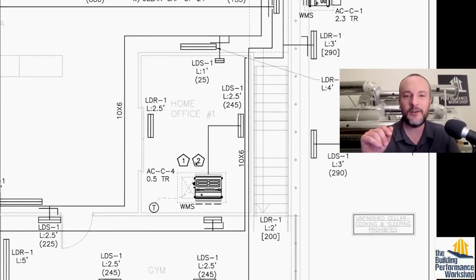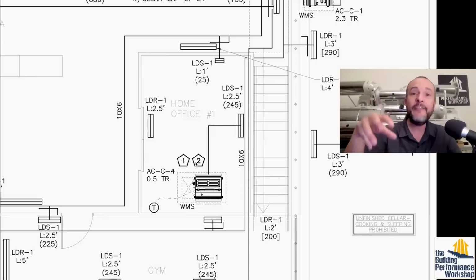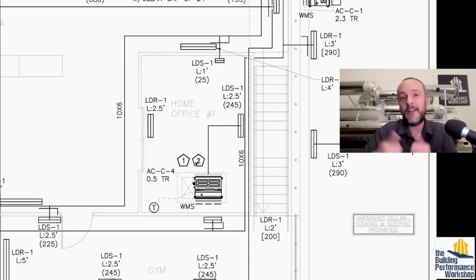This is like a 14,000 square foot home in New York, where there are lots of professionals and this, you know, the center of the universe, according to many people. And it's like they get things wrong a lot there too. That room is a classic example of one that has no load. Load is introduced by stuff inside the room that's giving off heat. If there's one human in that home office, which is probably likely, that human is going to be giving off 230 BTUs per hour of sensible heat, which is temperature heat, and 200 BTUs per hour of humidity or latent heat.